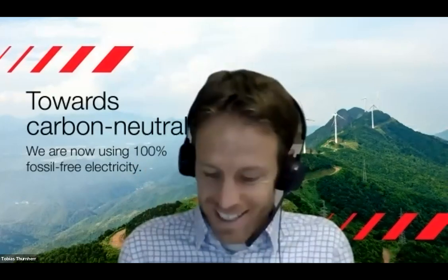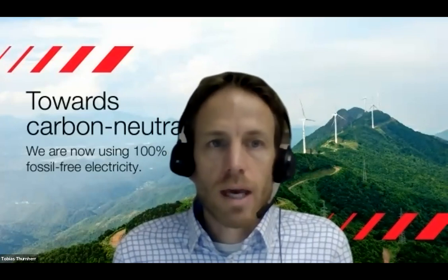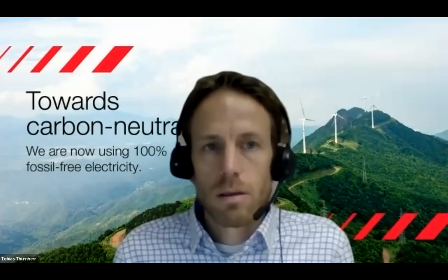Yes, definitely. Clive Kessel, are there any implications for 50 kV auto transformer arrangements? Also, the use of booster transformer to reduce inductive interference to adjacent telecom circuits. No, actually, the SFC can feed the system as a transformer, be this 25 kV, be it 50 kV. There is no difference there.